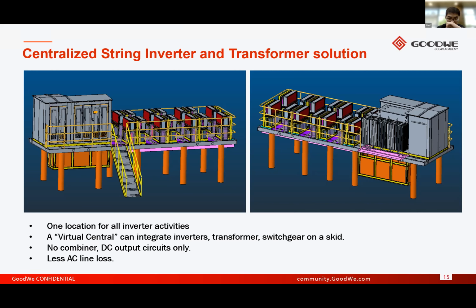This longer DC cable design will slightly raise the cost of the system, but what we gain is an easier O&M plan on large size, and you save on installation later as well. This has been done in very large applications right now in Qinghai province, China. We can install the inverter on an individual skid and build the frame close to the transformer pad. Through this, inverter troubleshooting and firmware updates can be performed remotely, which reduces the downtime. By the way, our inverter can remotely update firmware through PLC or RS485.